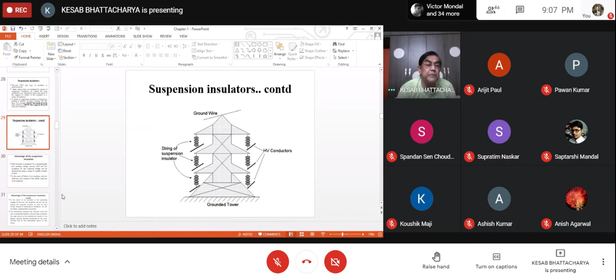Okay. Then let us now discuss advantages of suspension insulators. The first point that comes to mind is that when you make a suspension insulator for any system voltage, maybe 132 kV, maybe 230 kV, each individual disc insulator in a unit is rated for a comparatively low voltage, of the order of 11 kV, right? That is the first advantage.